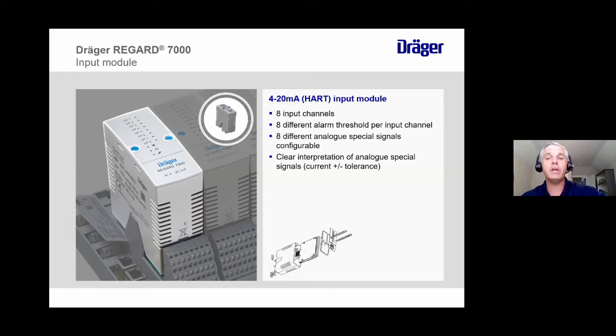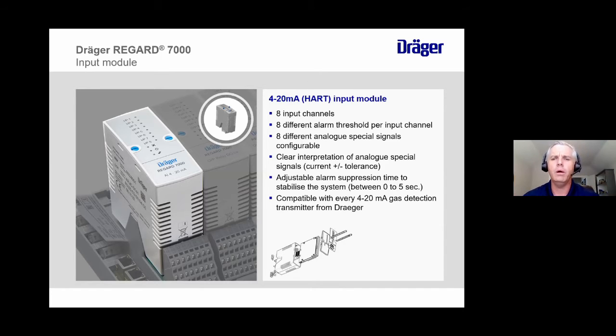There's also clear interpretation of those analog special signals. So we put a little deadband around, say, that 3 milliamp value, just to make absolutely sure that if we send out 3 milliamps from the detector, which means beam block fault, that fault is actually picked up at the Regard 7000. We also have adjustable alarm suppression time for the modules. So we want to make dang sure that the sensor is actually in alarm before we trip an actual alarm. This is part of the reliability of the system. The next slide I'm going to show you really hammers this home. And basically, it's compatible with every 4 to 20 gas detection transmitter from Draeger or basically anybody else. So you can connect other people's stuff to the Regard 7000 via the 4 to 20 as well.